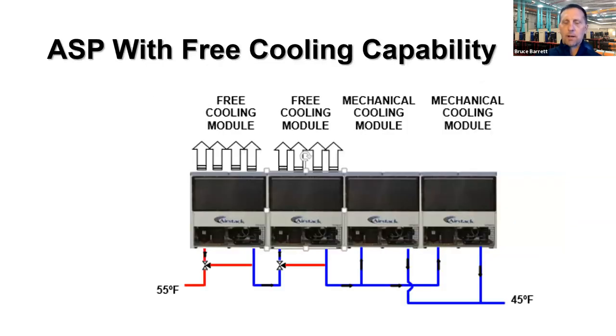All right, let's quickly talk about ASP modular chillers with free cooling modules. So this is just an example of how our free cooling works. If the ambient temperature is cold enough, we will send the water to that free cool module and pre-cool it in series with the mechanical modules. If it's too warm, our valve will not open. We bypass the free cools and we send our water to the mechanical modules. There may be a time we're doing partial free cooling as an assist, and then the mechanical modules are picking up the slack.